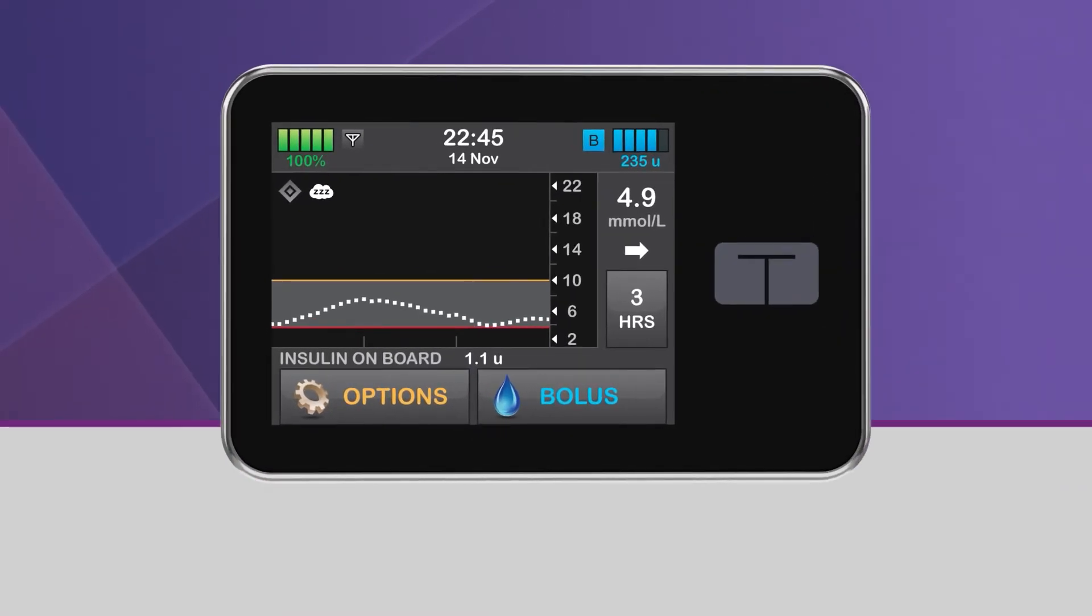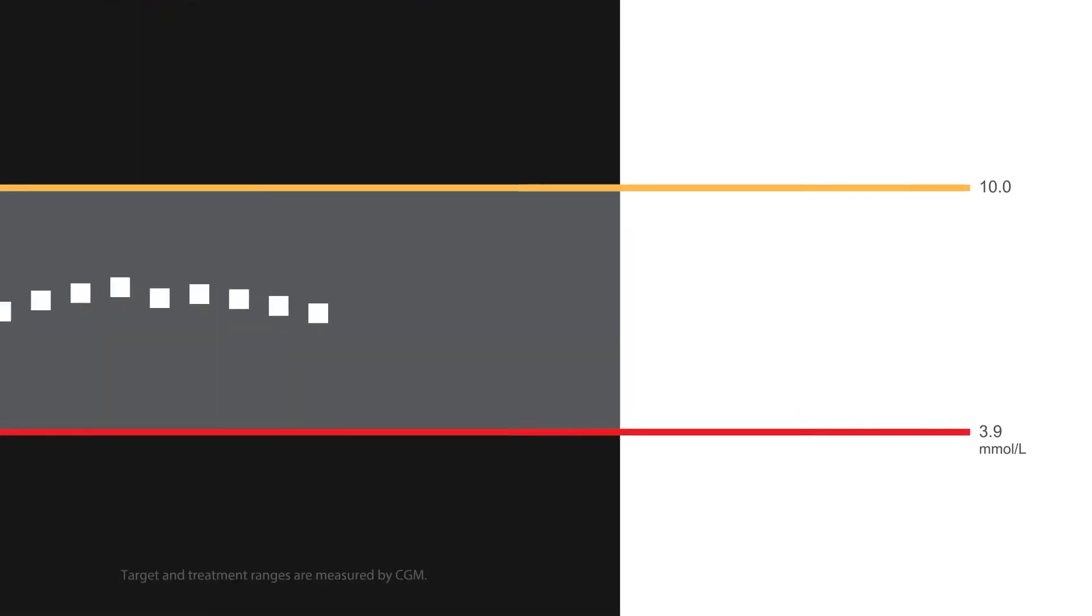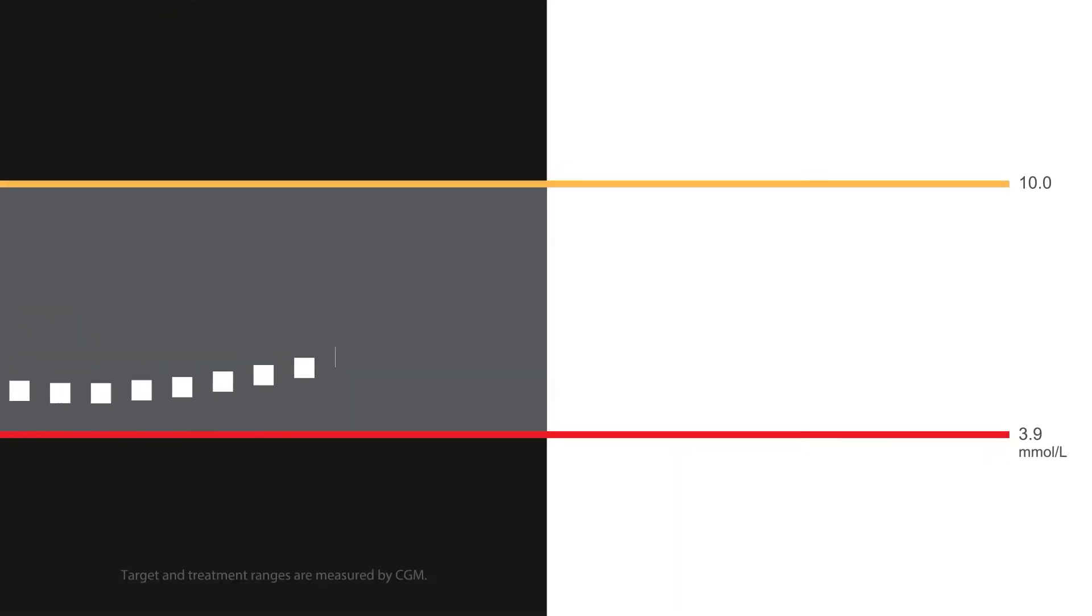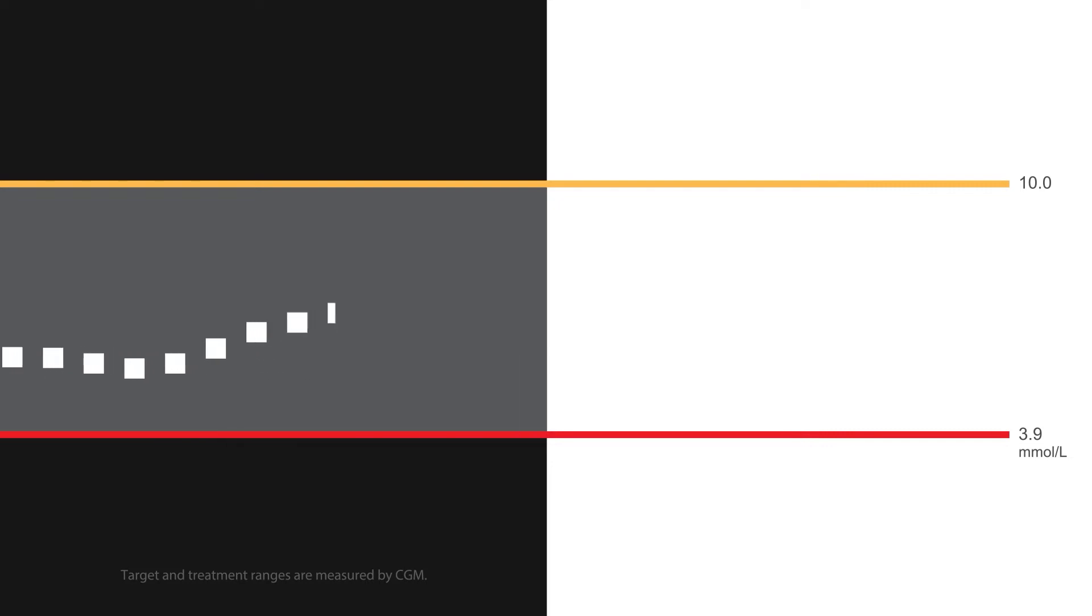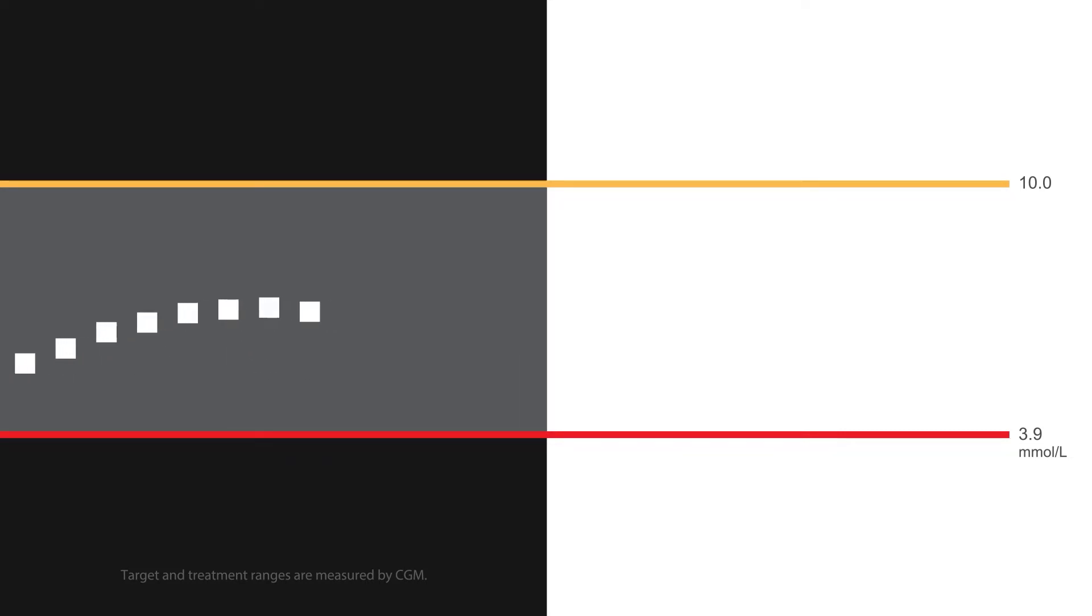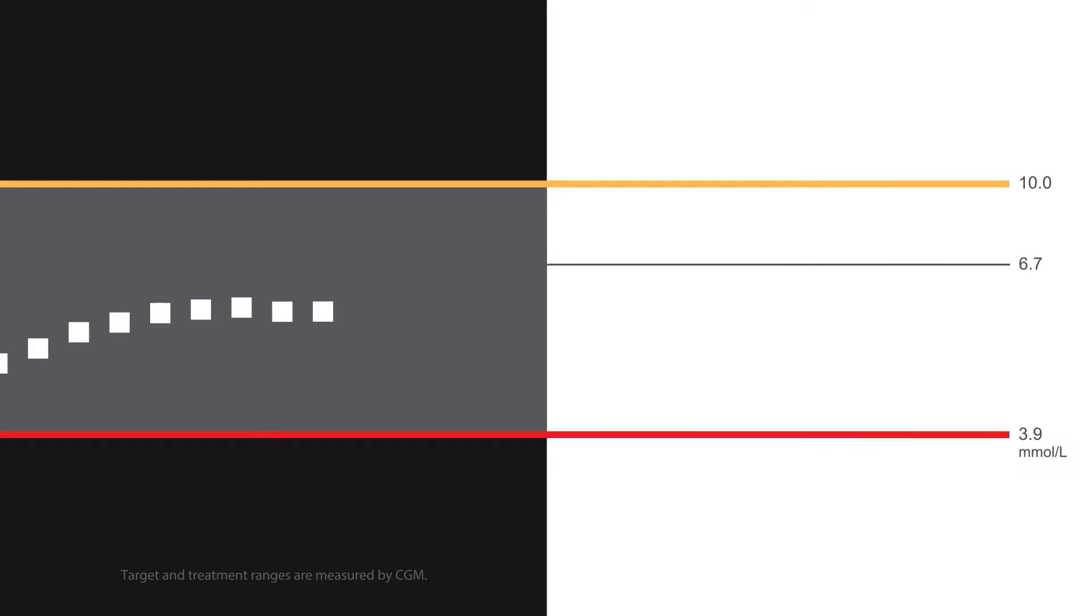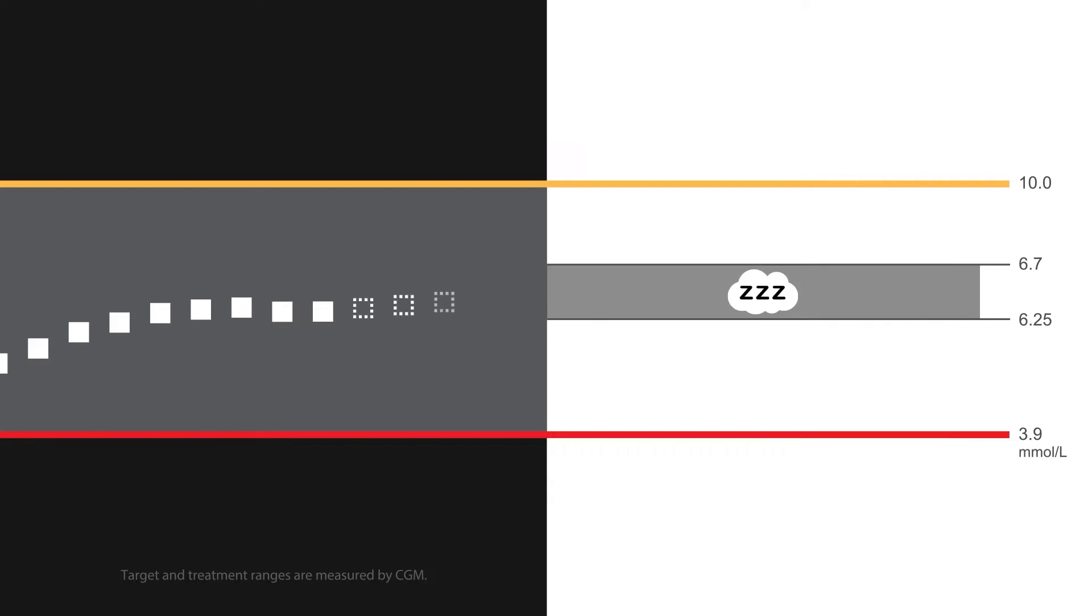A great feature of Control IQ technology is the ability to allow the system to target a narrower glucose range while you're sleeping. When the sleep activity is turned on, either manually or by using the sleep schedule function, the upper limit of the Control IQ treatment range changes from 10 millimoles per liter to 6.7 millimoles per liter, keeping the lower limit at 6.25.